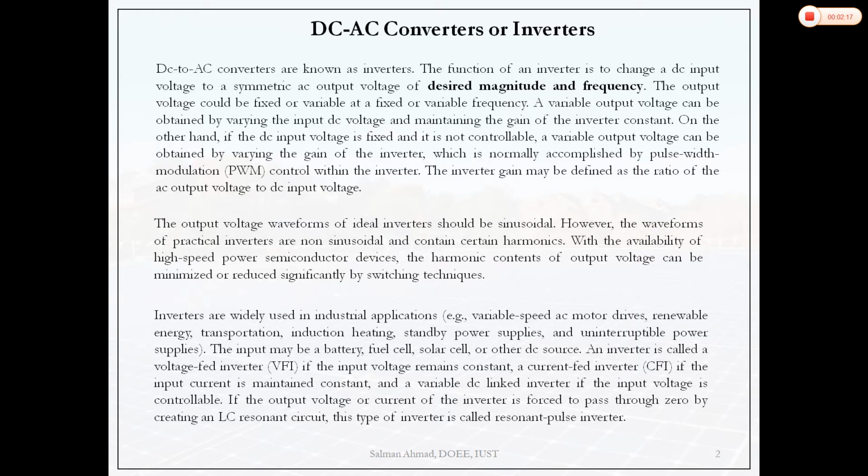The output voltage waveform of an ideal inverter should be sinusoidal, but you will find that in inverters actually you are getting a non-sinusoidal waveform. So that waveform you can decompose into a fundamental component and harmonic components. The fundamental component will be the desired part, and the harmonics part we have to filter out. In most of the cases you will find that the low order harmonics are the more problematic because their magnitude is significantly high.